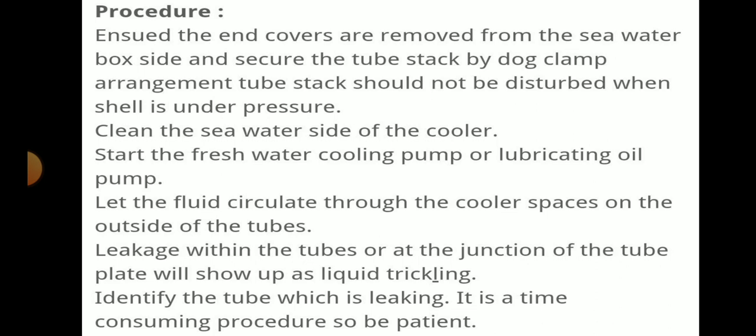So we have to ensure that the end covers are removed from the seawater box side and secure the tube stack by a dog clamp arrangement. The tube stack should not be disturbed when the shell is under pressure. We have to first ensure that the end covers are removed from the seawater box side and secure the tube stack by a dog clamp arrangement.